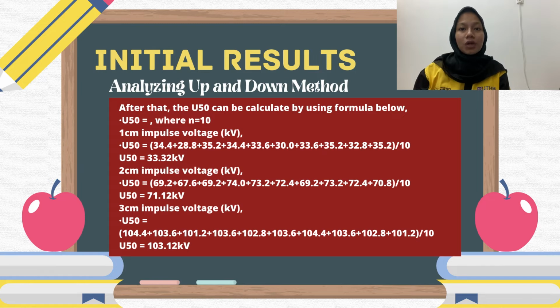Since I did not have much time, I only did 10 shots, though the minimum number of shots required is 20. For 1 cm we get 33.32 kV, for 2 cm we get 71.12 kV, and for 3 cm we get 103.12 kV. From here, we can conclude that the larger the gap length, the harder it is for the electrodes to break down, because more voltage impulse is needed to break down the air.